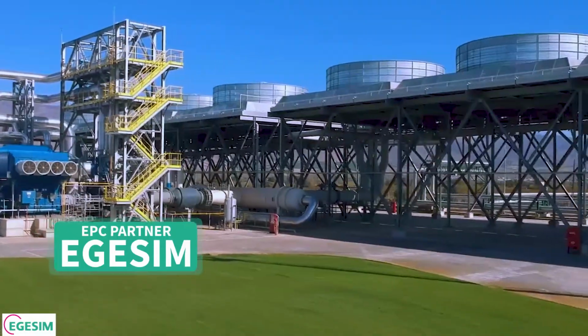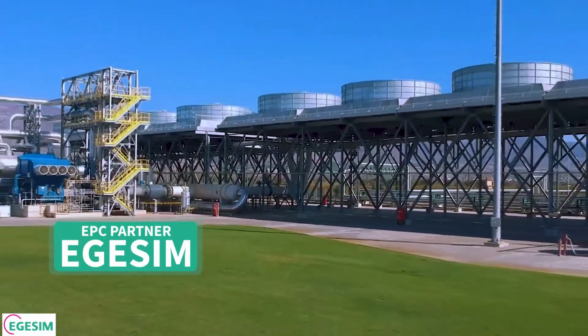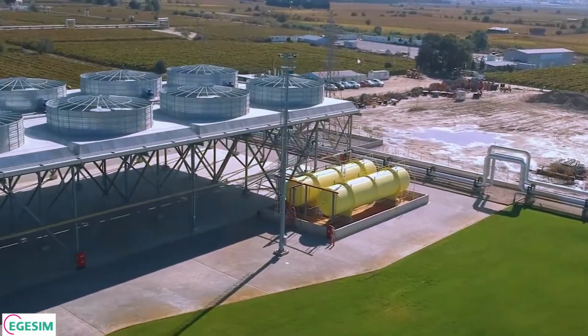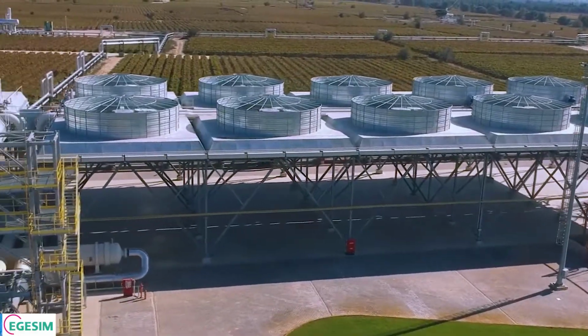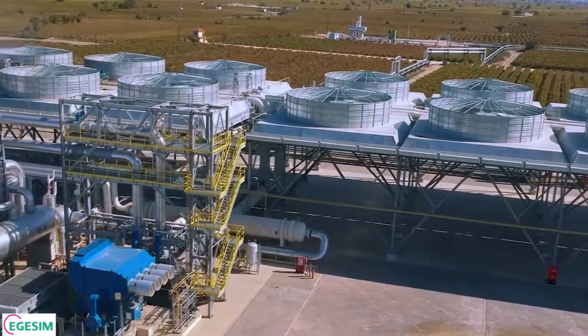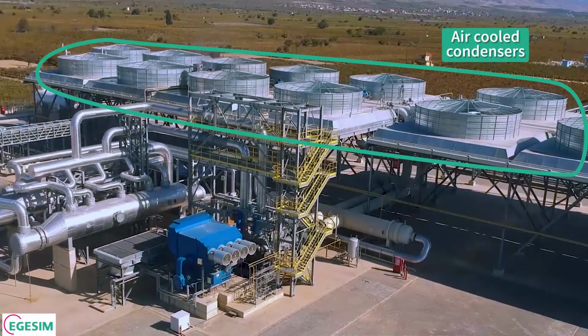And while of course the whole power plant is a beautiful piece of engineering, the most dominating part is the air-cooled condenser, or ACC. The ACC consists of heat exchangers and some fans that pull the air from the lower side to the upper side. Thus it cools the bundles, which are called bays, and it's rejecting the heat from the butane gas into the ambient air. But before the butane gas is entering the ACC, the remaining heat after the expansion process is taken out to preheat some more gas before it's evaporated. This is done in the recuperator.